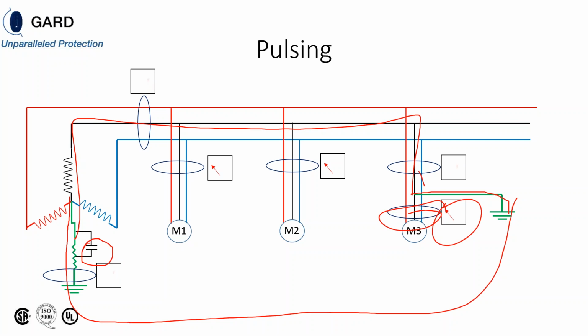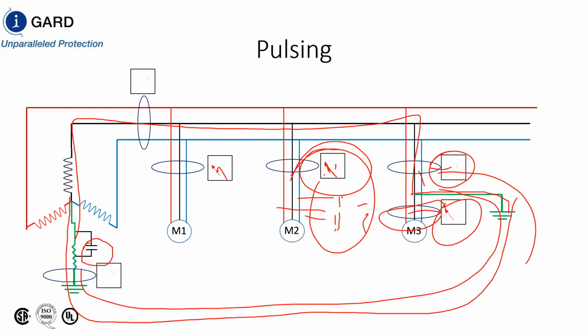this method. Now, the second part of that question was, do you still need feeder indication? I think you do, because the problem is this is an ideal situation. Unfortunately, in a non-ideal situation, you're going to have capacitances on every system to ground, so you're going to have a little bit of current on every feeder, measuring that capacitive coupling. But only in the faulted path will you see this pulsing, because this capacitance coupling here is going to be voltage dependent, and the signature of the current going through here, through the fault, is going to be impedance dependent. So you need to change the value of the resistor to actually pinpoint where your fault is. Long answer, but I hope you understand it.